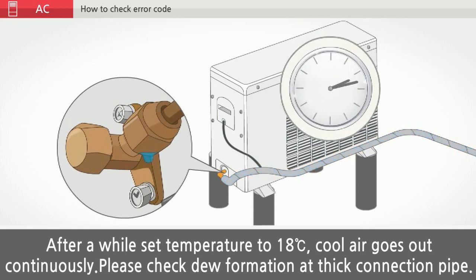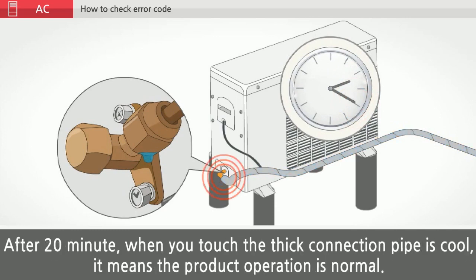Please check for dew formation at the thick connection pipe. After 20 minutes, when you touch the thick connection pipe and it is cool, it means the product operation is normal.